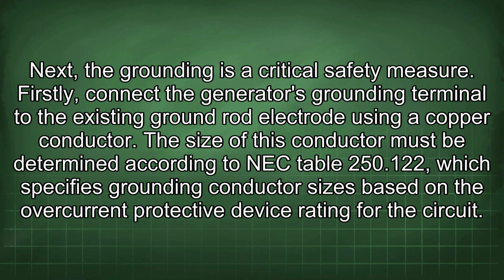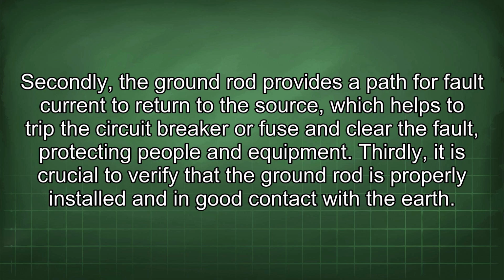Next, the grounding is a critical safety measure. Firstly, connect the generator's grounding terminal to the existing ground rod electrode using a copper conductor. The size of this conductor must be determined according to NEC Table 250.122, which specifies grounding conductor sizes based on the overcurrent protective device rating for the circuit. Secondly, the ground rod provides a path for fault current to return to the source, which helps to trip the circuit breaker or fuse and clear the fault, protecting people and equipment. Thirdly, it is crucial to verify that the ground rod is properly installed and in good contact with the earth.